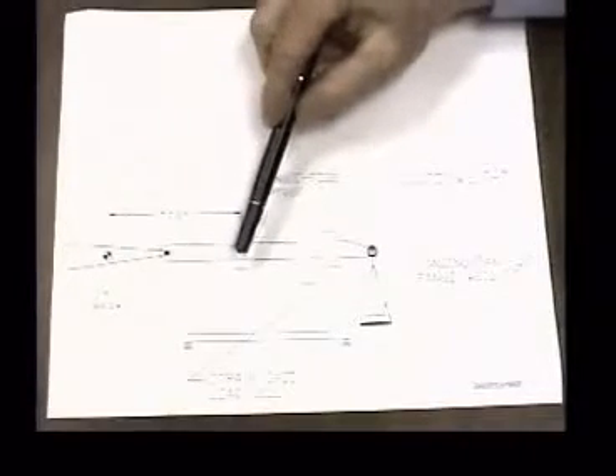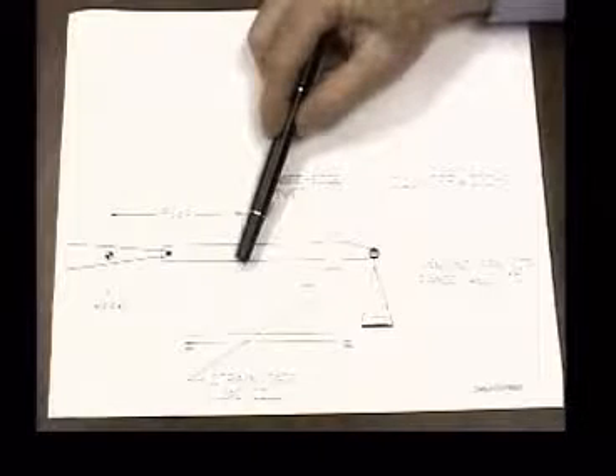Now, I mentioned that this method was developed in the 1950s. Amazingly to us, when we first got into this business in the 1980s, we discovered that all of the moment weight machines that were being sold still used the old technology. It has a number of serious fundamental drawbacks. One of them is that the knife edge pivot has to be so narrow that it is very fragile. It has to be probably 20 or 40 millionths of an inch wide in order to achieve the accuracy you need for modern moment weight specifications. And obviously an edge as sharp as that will break down almost immediately under repeated use in a production environment.